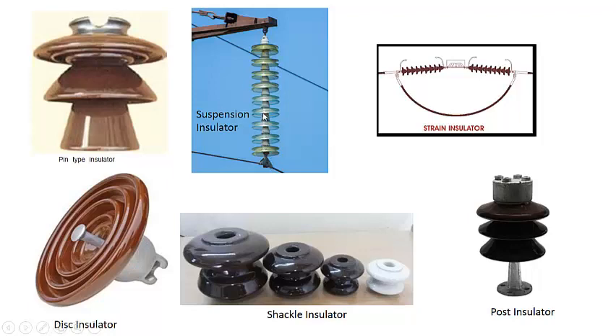So strain insulator, again this is the same disc insulator connected in series but in a horizontal direction because there will be a net force on this transmission line or on this tower. So to bear that net force, we have to use these type of insulators in this configuration. These are the different shackle insulators for different voltage levels. They are used as strain insulator for low voltage level.